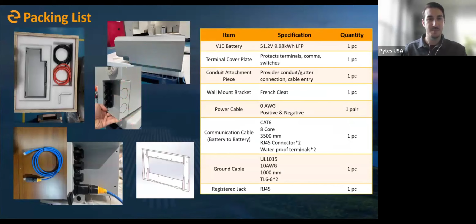So this is what it looks like normally, and I think it does a really good job of showing where the Wi-Fi dongle installs. Using these two pieces that are included with the packing list, your terminal cover plate and your conduit attachment piece, converts this to what you'd see with the floor mount. Those two pieces can be installed — it covers up all of our breakers, our power buttons, our comms ports, our power cables, and gives us a point or an interface where we can run conduit in and out of the battery.